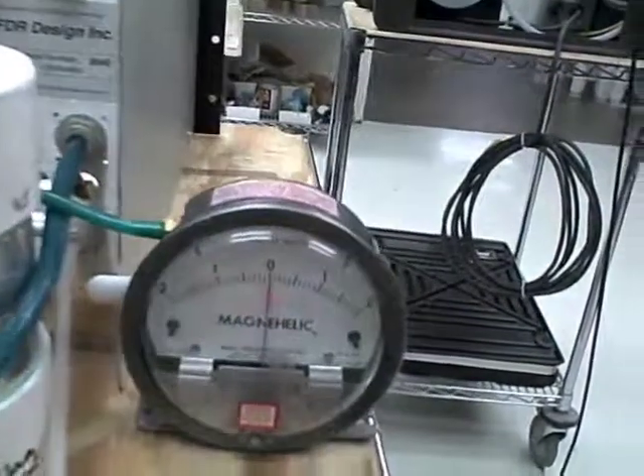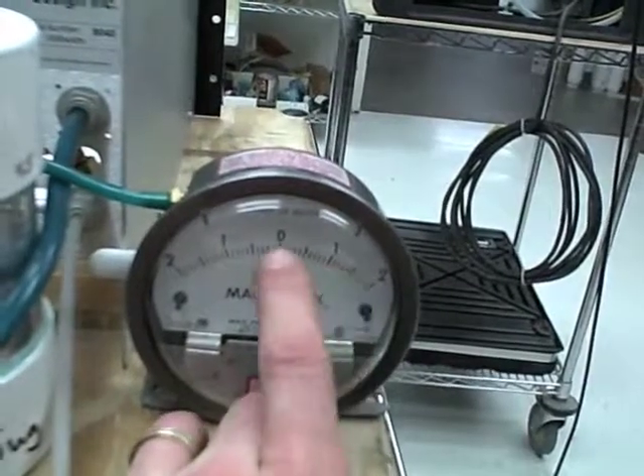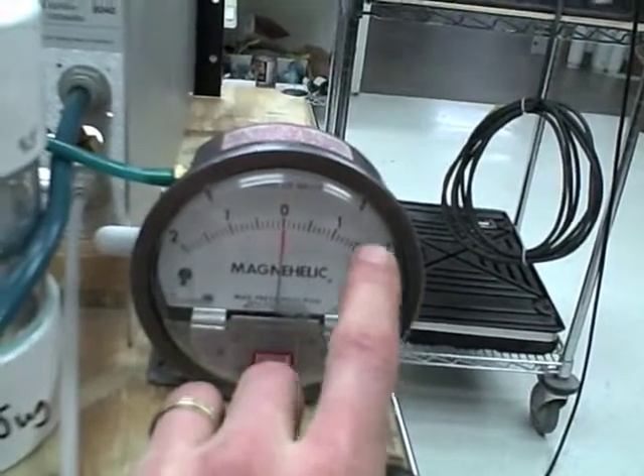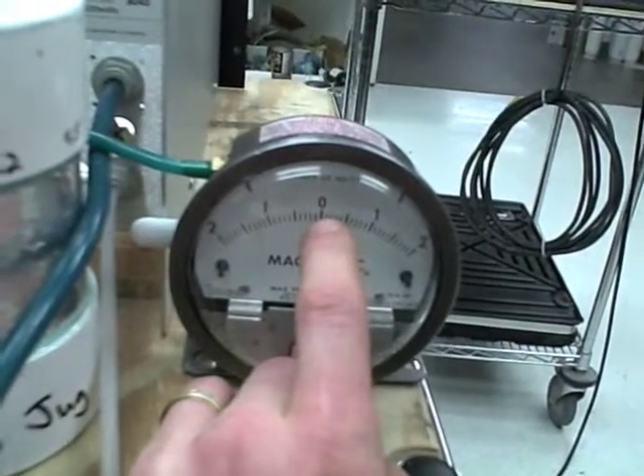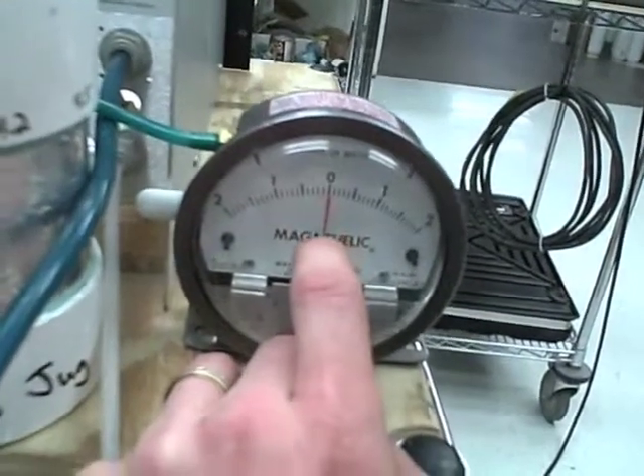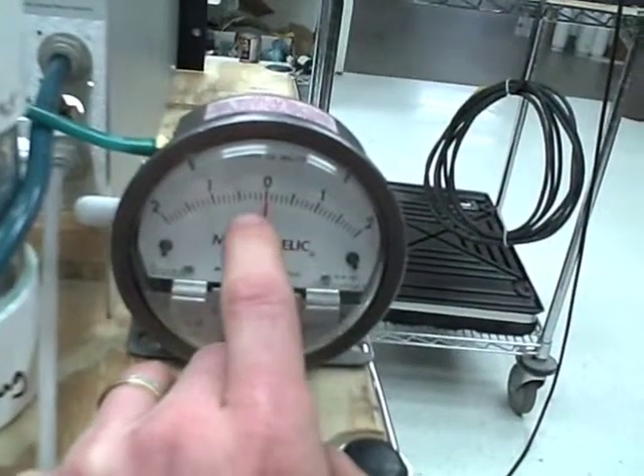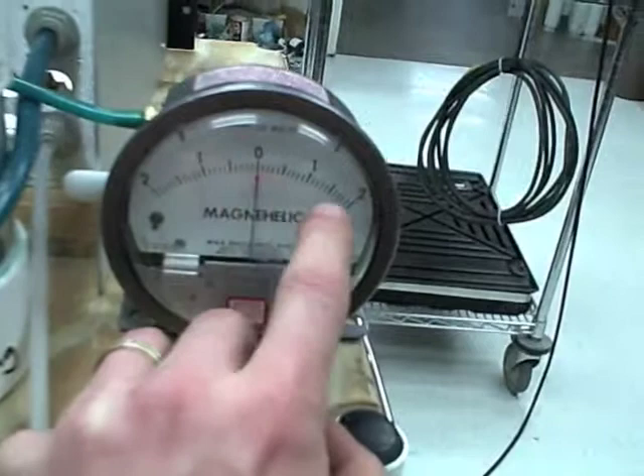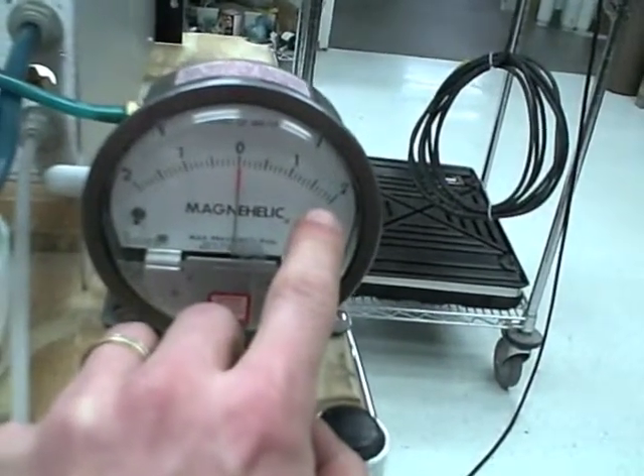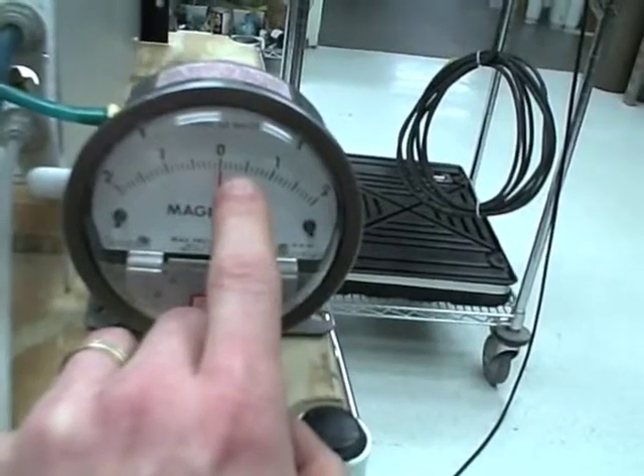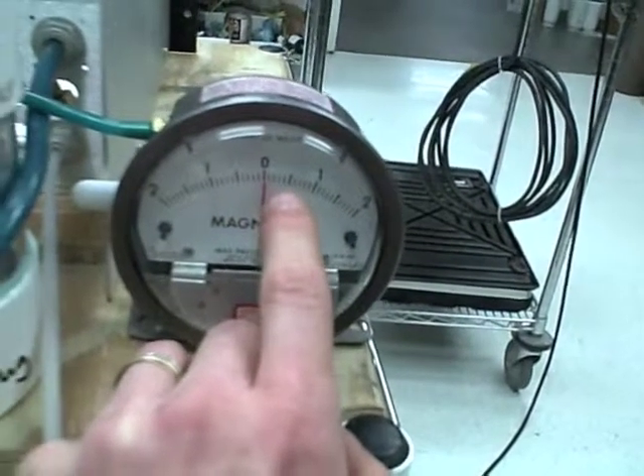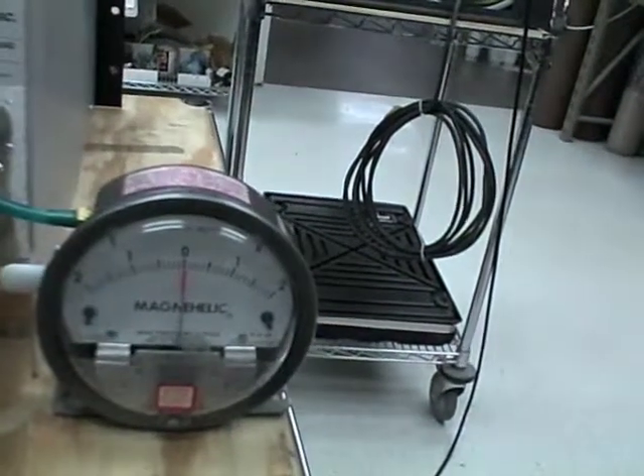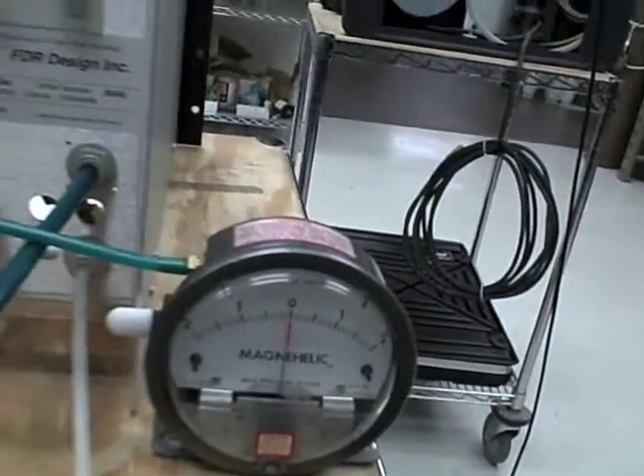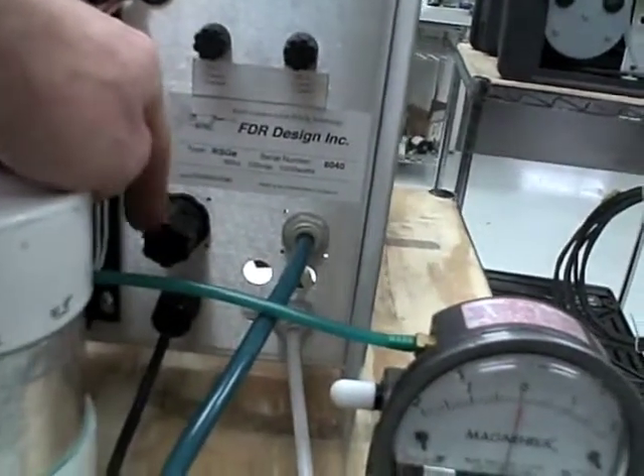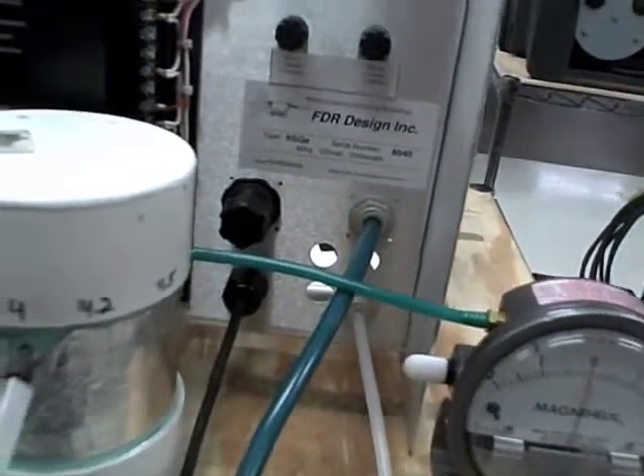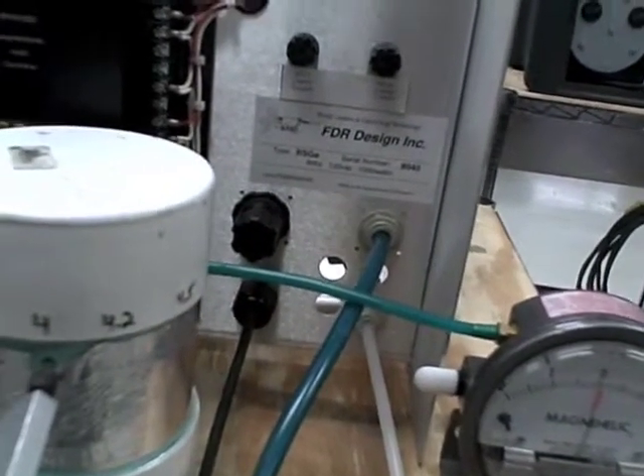So how that's going to reflect on the gauge is anywhere positive. So we want it between 0 and 2. We don't want it negative. That means that there's more vacuum getting sucked out than argon going in, and that's a condition that we don't want. We want it just positive, so somewhere in this range. The nominal setting is 1/2. So that's where we're going to set it right now when we do this, and we're going to adjust that with this regulator on the back of the machine here. So we'll turn it to the right or clockwise to increase the argon pressure.